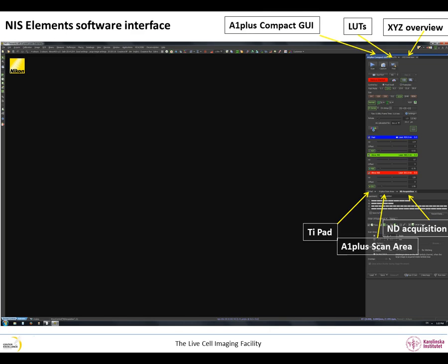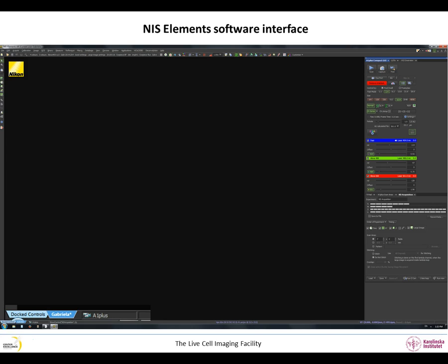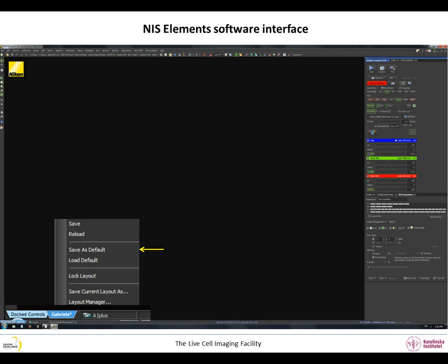The NIS Elements acquisition software works with tabs. The starting layout has six tabs. The NIS Elements software is used by many users, but each user has a customized layout with the tabs he or she uses. If you want to save your own layout, right click on the Docked Controls tab, choose Save Current Layout As and give it your name. You can now right click on the new layout and save it as default. If you accidentally close one of your tabs, right click on your layout to reload it.